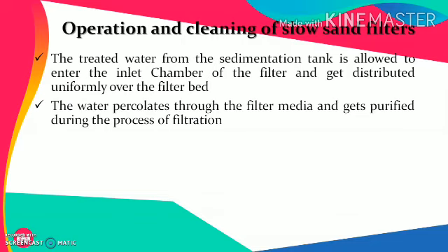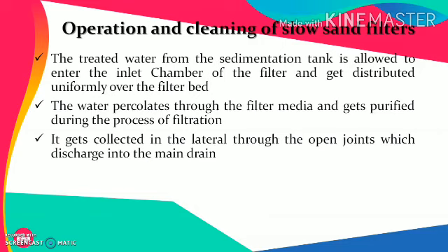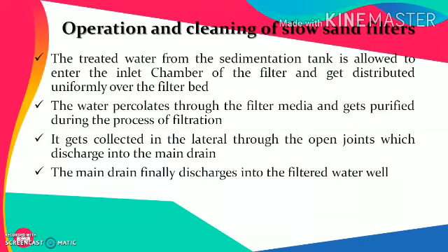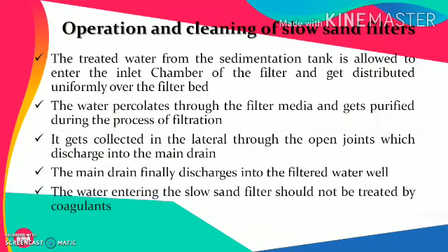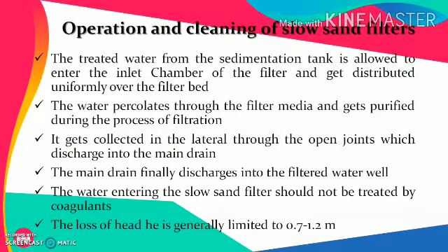The major processes happening in this kind of filter are mechanical straining and metabolism. The water gets collected in the laterals through the open joints, which discharge into the main drains. The main drains finally discharge it into the filtered water well. The water entering the slow sand filter should not be treated with coagulants, as discussed earlier.